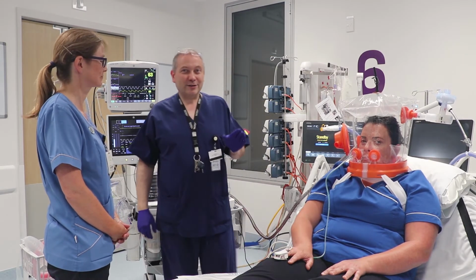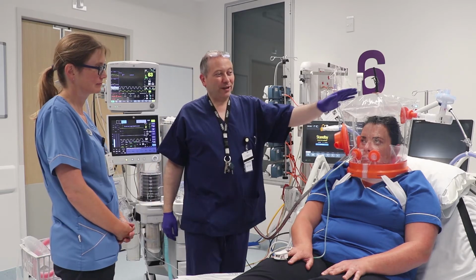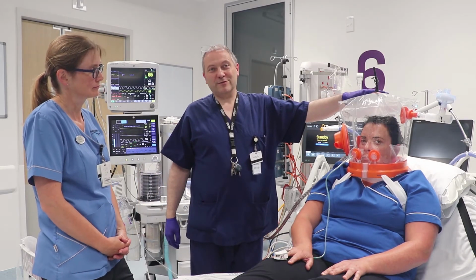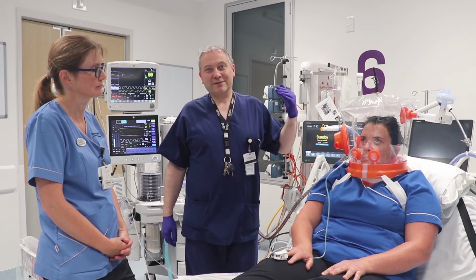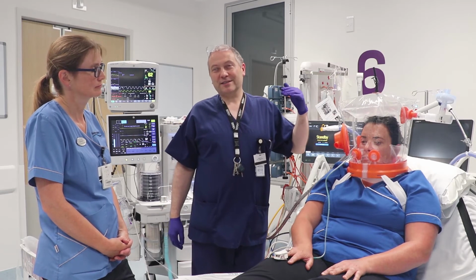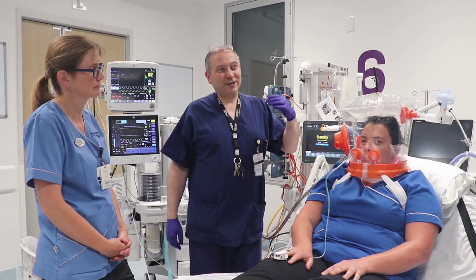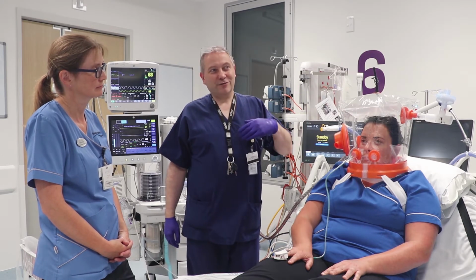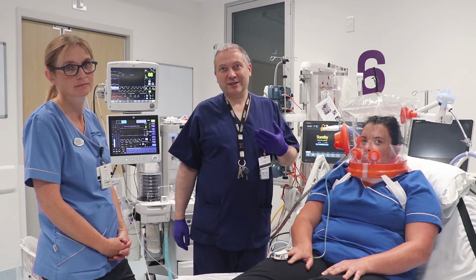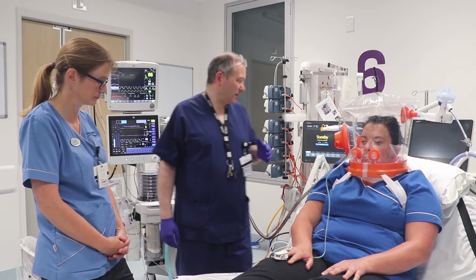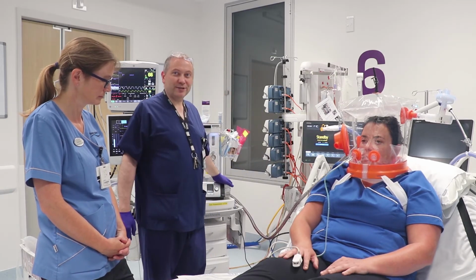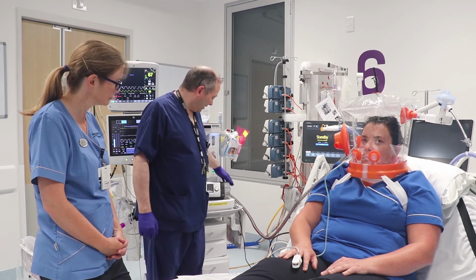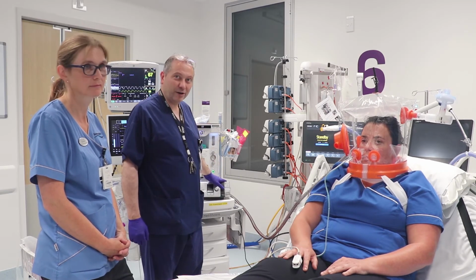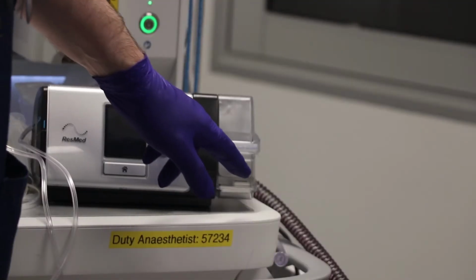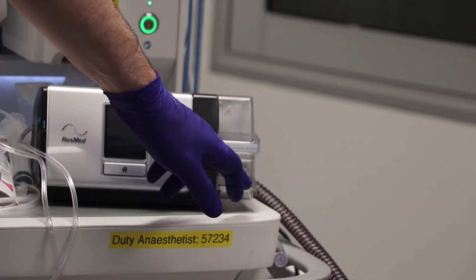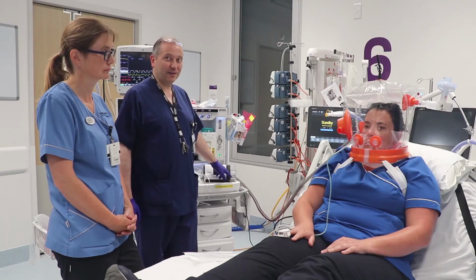Now, the last thing to note is that when in the helmet, or on any other form of CPAP, you have a very high gas flow rate. And it's important that the gas is humidified, otherwise we dry out the cilia and reduce the ability of the patient to expectorate and clear secretions. In the ResMed Lumis, the humidification comes from this water reservoir, which we should be regularly monitoring to check that there's water somewhere between the minimum and maximum levels.